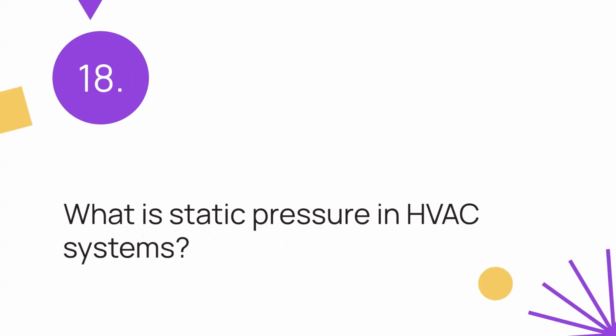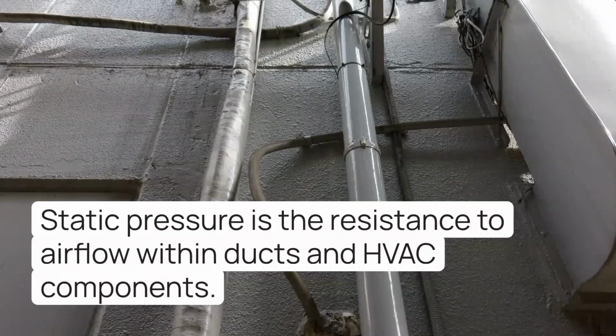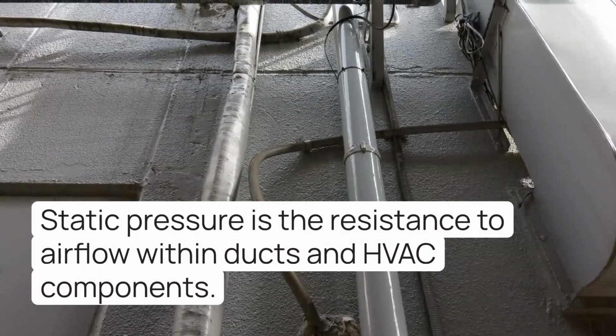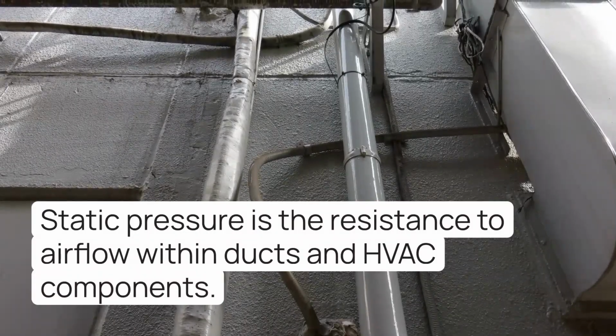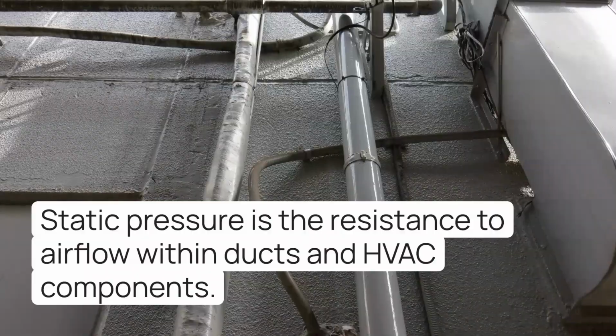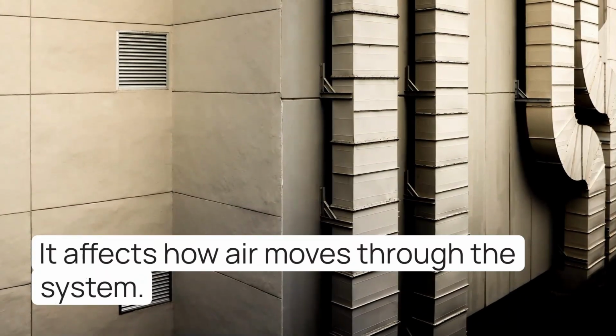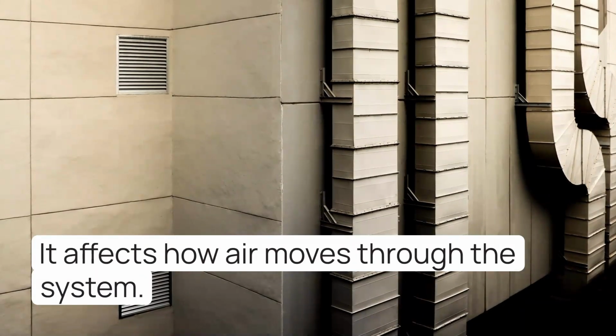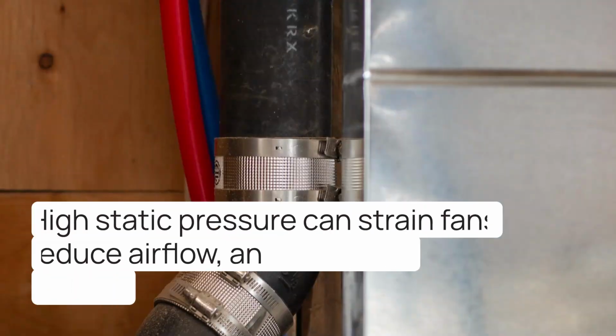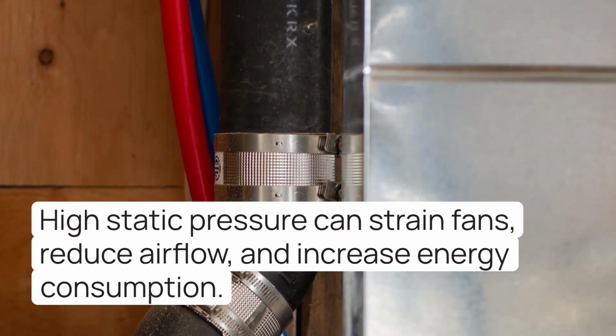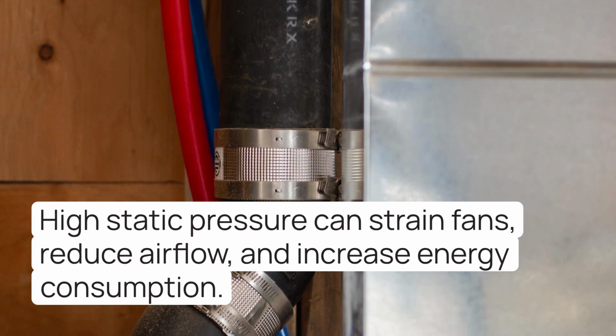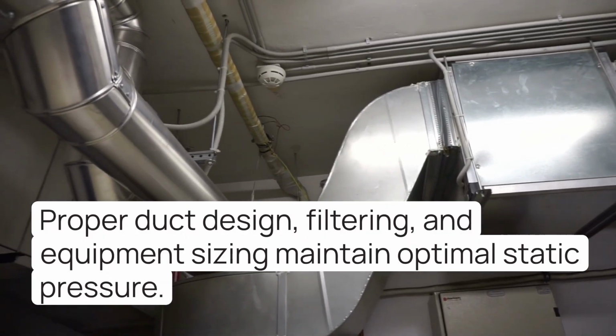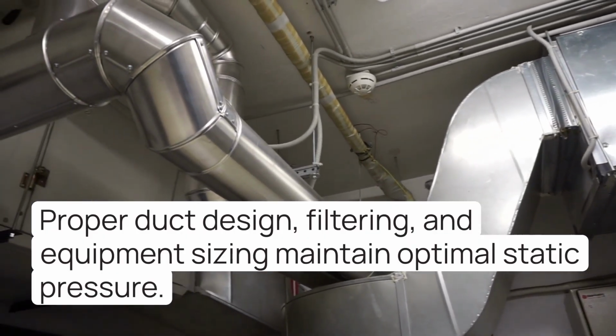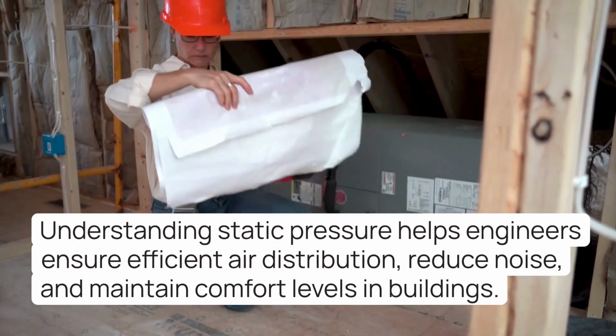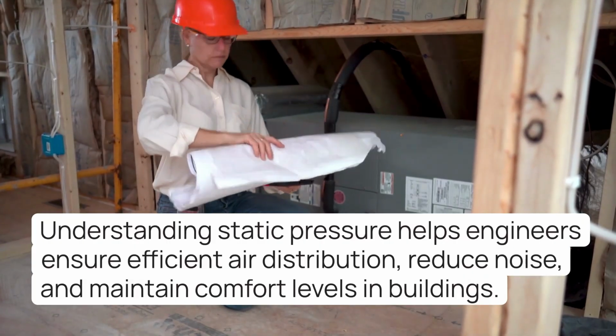18. What is static pressure in HVAC systems? Static pressure is a resistance to airflow within ducts and HVAC components. It affects how air moves through the system. High static pressure can strain fans, reduce airflow, and increase energy consumption. Proper duct design, filtering, and equipment sizing maintain optimal static pressure. Understanding static pressure helps engineers ensure efficient air distribution, reduce noise, and maintain comfort levels in buildings.